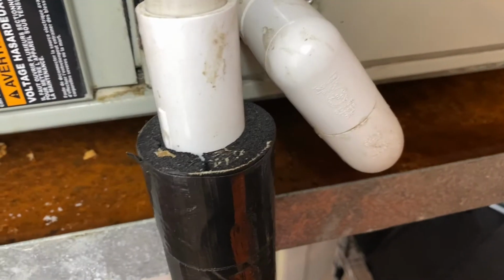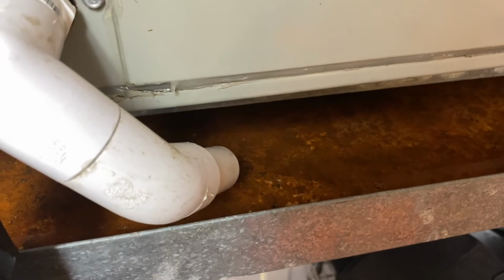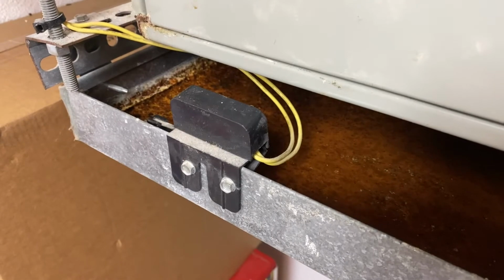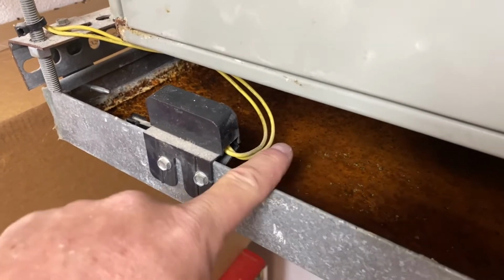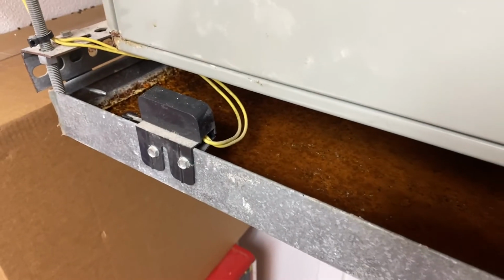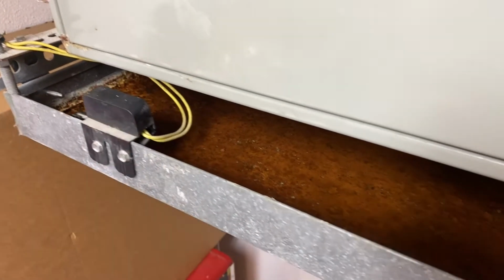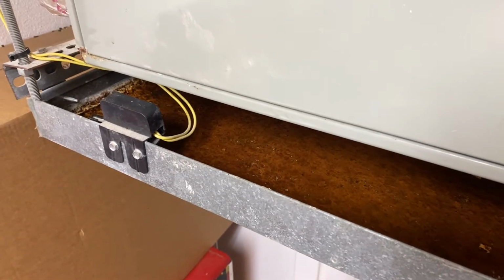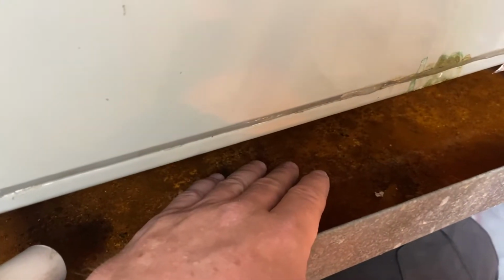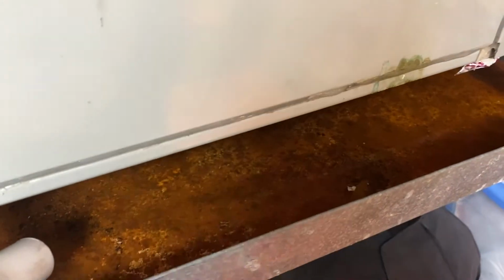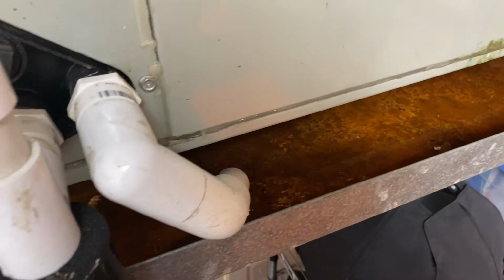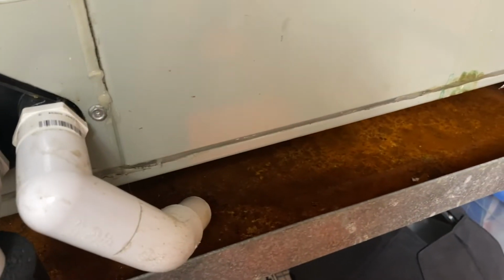But if this remains clogged, it's eventually going to fill up the pan. So it's got a little cutoff switch so that when the pan gets full, it's going to turn off your air conditioning system. And that's usually what happens. If this cutoff switch is activated, the screen goes blank on your thermostat. So the thing to look at is, look inside this pan. Now, I've already sucked all the water out of it, but if this has water in it, then you know that you've got a blocked condensation line. So I'm going to show you how to fix it.